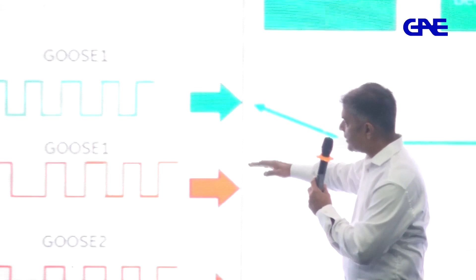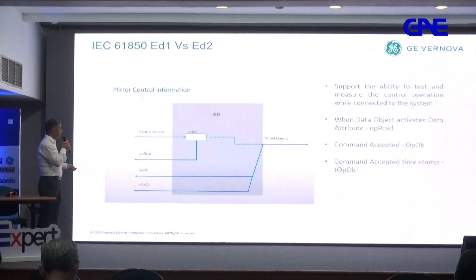Okay, then also if you test your equipment, how do you check the response, right? For conventional equipment, what I need to do is to inject current, voltage, whatever, and I check the response of digital output, which is my output relay. Okay, in digital substation what can we do? Because that's my IED, and normally I connect my test equipment on the output and see if it is operated or not. But in 61850 there is a possibility to monitor this point. So this point is op, so you can monitor this attribute. So this is how you can accomplish testing.